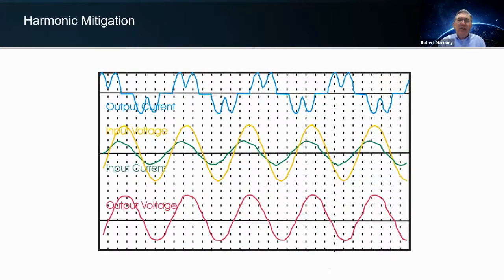Here's a harmonic mitigation slide. The top slide shows about a 50% current harmonic on the load side coming in. And then you can see on the bottom, your output voltage does not reflect any of that. It's the nice clean output voltage of the UPS to your loads, giving your loads what they need. That's probably showing about a 5% voltage deviation from that 50% current harmonic to the load. And then the input voltage and current, as you can see, the waveforms are nice and clean.